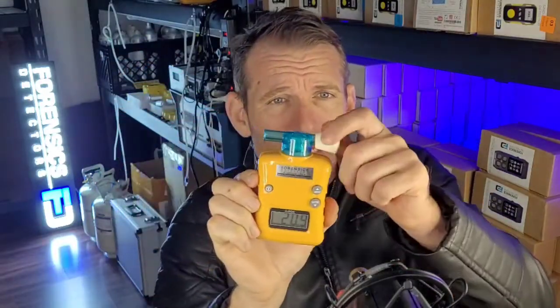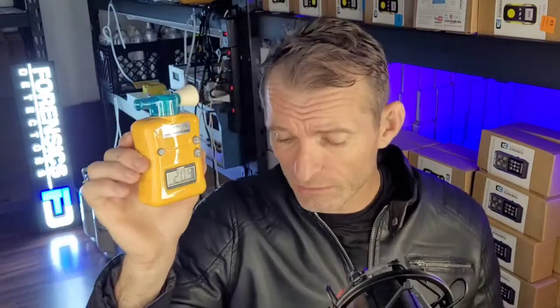Another one I love is our scuba meter detector, or what we call our oxygen analyzer for scuba. It's made for scuba because those scuba people want to check their tanks. We have made a special dome where you pop it onto your valve and you can detect the oxygen from zero to 100%. This is the only detector in our line that does a true zero to 100%. It uses a Honeywell sensor — not many sensors are capable of doing that. It's a very unique and versatile arrangement. You could do depletion, you could do enrichment of oxygen. It also comes with an attachment so you can pop it onto your oxygen concentrator and detect the oxygen from the machine — just make sure the flow isn't restricted by the dome cap. We want to grab as much market share from those incumbents as possible.